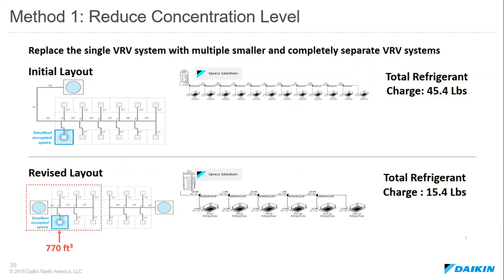Another way that we can reduce our concentration level would be to replace the single VRV system with multiple smaller and completely separate VRV systems. So at the top of the page, I'm showing you our initial layout where we have a total refrigerant charge of 45.4 pounds. And then we have a revised layout below at the bottom of the screen. In that revised layout, we took the system and split it up into two smaller systems. This allowed us to even more greatly reduce our total piping, which of course reduces cost, and also reduce, most importantly, our total refrigerant charge. So now our total refrigerant charge per system is going to be 15.4 pounds.